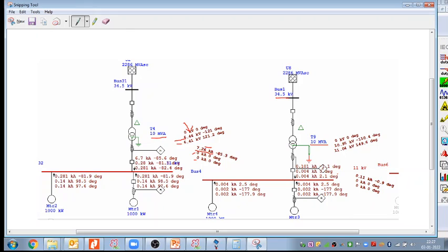Now when it comes to NGR grounding, we can see that when I put the NGR, yes, we can limit the fault current very well. 0.101 kiloampere, meaning 100 ampere, is what I wanted to limit. What is the drawback here? Initially 6.44, now it jumps to 11 kilovolts, right? My phase voltage jumps to 11 kilovolts, right or not? As we can see through the simulation result also.